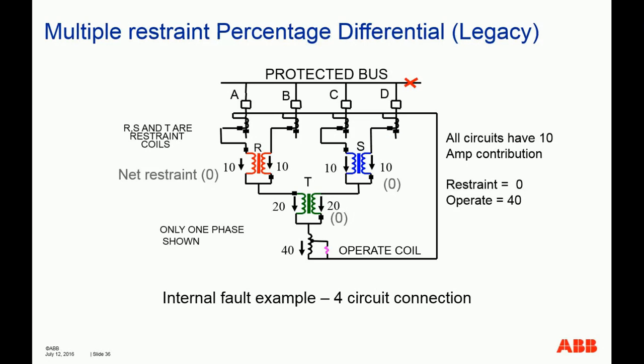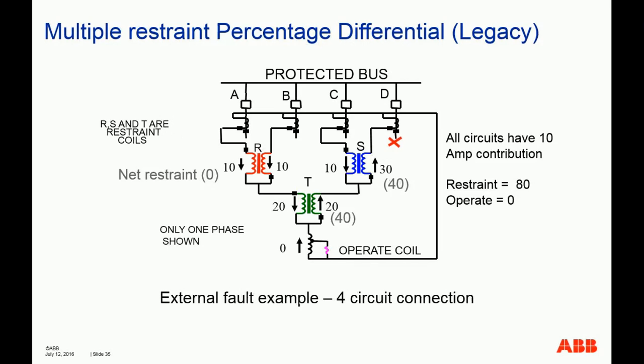The next slide shows that for the same type of bus configuration and the same type of relay wiring, for internal faults, since all the current goes in the same direction through the operate coil, there's no restraint, and the operate current is higher than the restraint. And how do we use this restraint?